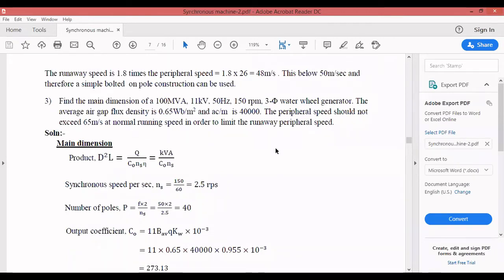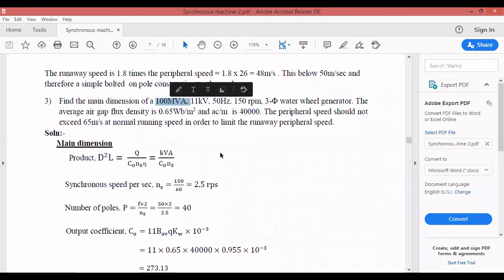Now a third example: find the main dimensions of a 100 MVA (note: convert to kVA by multiplying by 10³), 11 kV, 50 Hz, 150 RPM, three-phase water wheel generator. The average air gap flux density is 0.65 Wb/m² and ac = 40,000 A/m. The peripheral speed should not exceed 65 m/s at normal running speed in order to limit the runaway peripheral speed.